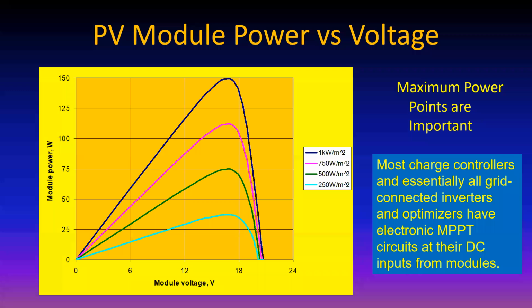And most charge controllers and essentially all grid connected inverters and optimizers, which is a new kind of device that we'll talk about later, they all have electronic maximum power point tracking within the device, and it's at the DC input coming from the modules. So maximum power point tracking is pretty straightforward electronic circuit design, and there's essentially no system out there being designed now, unless it's something really, really small, that doesn't take advantage of maximum power point tracking.